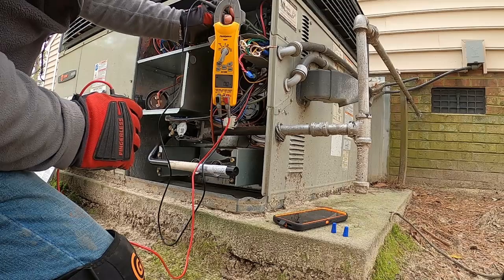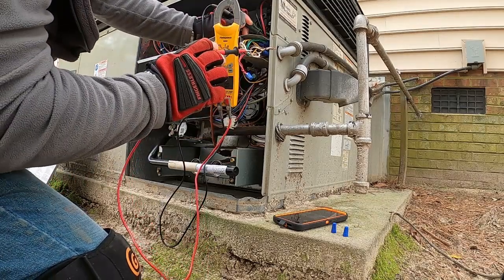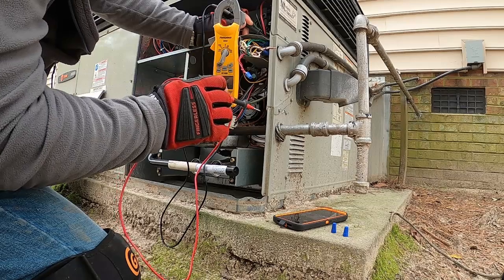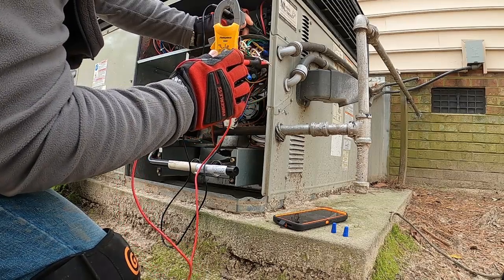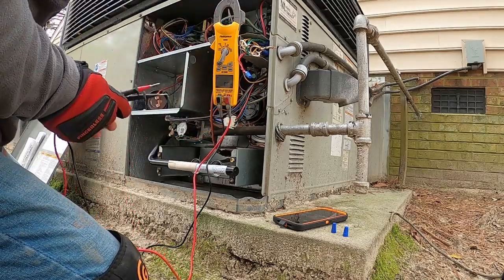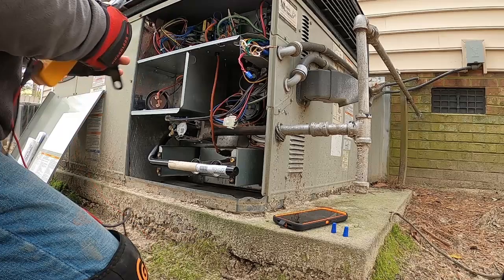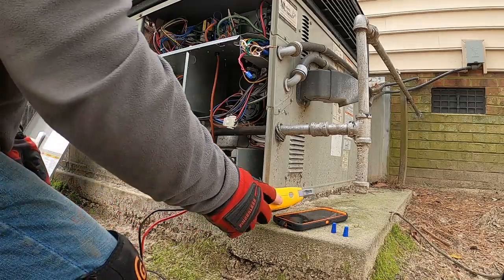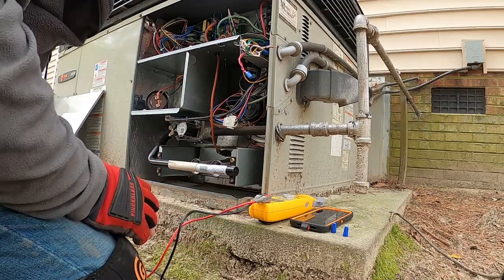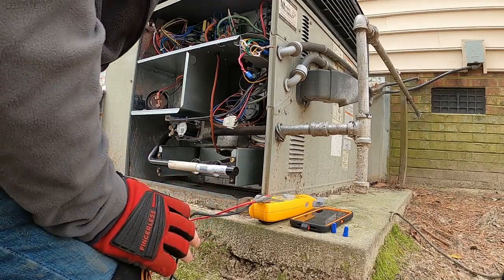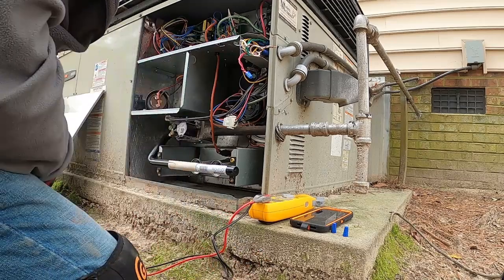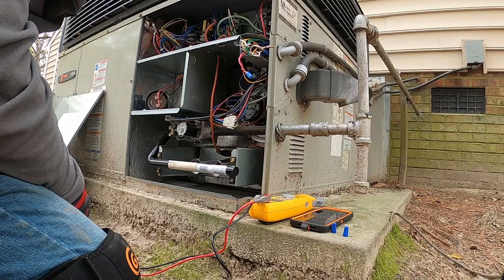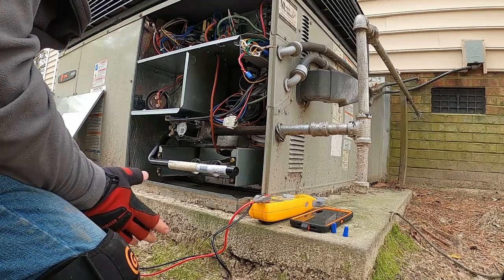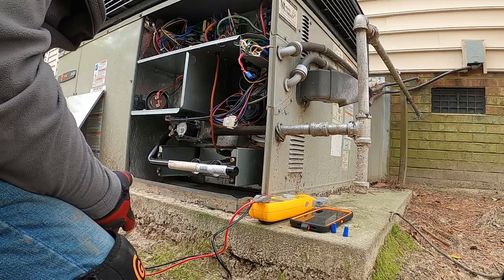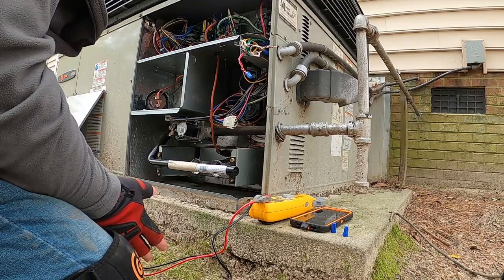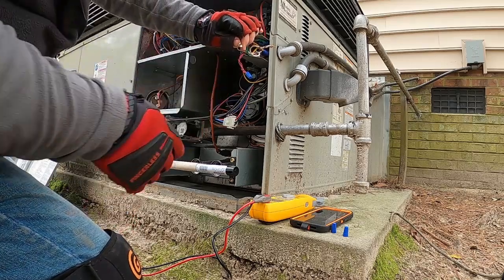Let's see what we're getting here. So we are getting a 24 volt call on the first stage. We are not getting a call as yet for second stage. We'll double check. He put in a 2-stage Honeywell wireless thermostat, I think it's a 6000 series. So I have to double check that. I got it set for 65 inside, and it's 56 in there, so it should be turned up high enough to call for both stages.